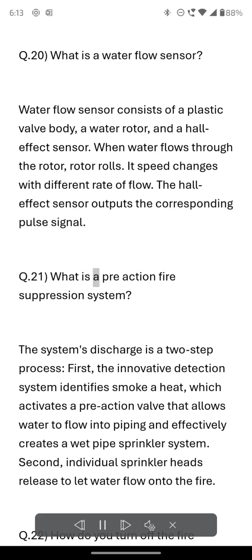Q.21 What is a pre-action fire suppression system? The system's discharge is a two-step process. First, the innovative detection system identifies smoke or heat, which activates a pre-action valve that allows water to flow into piping and effectively creates a wet pipe sprinkler system. Second, individual sprinkler heads release to let water flow onto the fire.